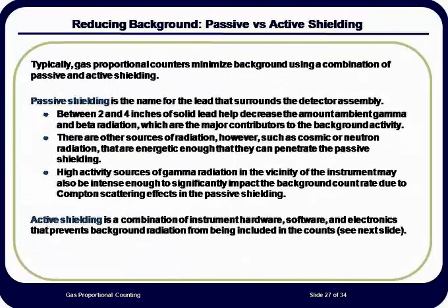If radioactive sources containing gamma rays are kept in the same room as the gas proportional counting instrument, they can also create background radiation through bremsstrahlung and Compton scattering that can elevate detector backgrounds. Active shielding combines electronics and additional detection devices to minimize background.